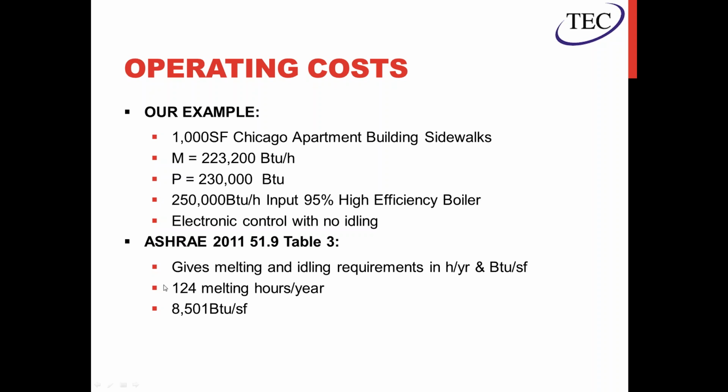So this is telling us that there are 124 melting hours per year in our area, and that the yearly load would be 8501 BTUs per square foot.